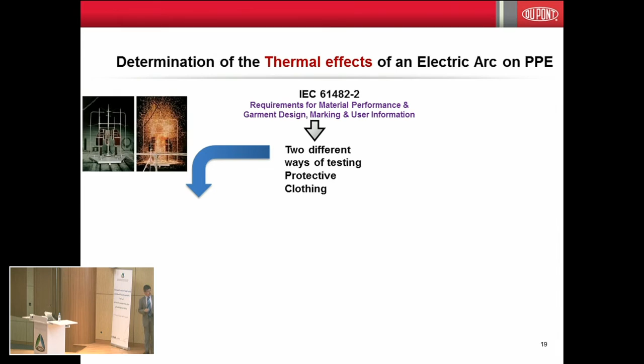In this case, what we're doing is determining what we call the incident energy that will impact the garment. This is the test called the open arc test. As you can see in the picture, once you generate the arc in the middle of the equipment, it will basically blow out in all directions—top, bottom, left, right. So the arc is not constrained; it's open arc.